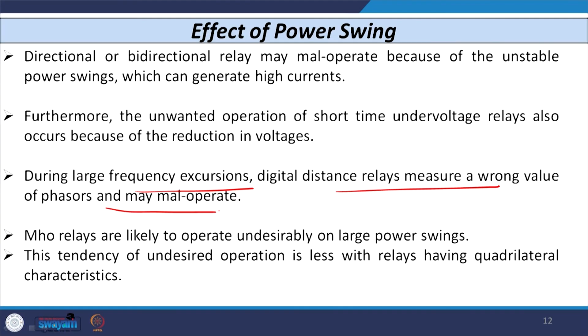To avoid this, we need to add either a power swing blocking function, or we need to use some other different philosophy. Now, to understand the power swing phenomenon, you can look at this figure. I have shown the 3 zone characteristic of the Mho relay. This is the first zone, second zone and third zone of the Mho relay, and I have also shown with a dotted line the quadrilateral characteristic, and the locus of power swing shown by the value R.